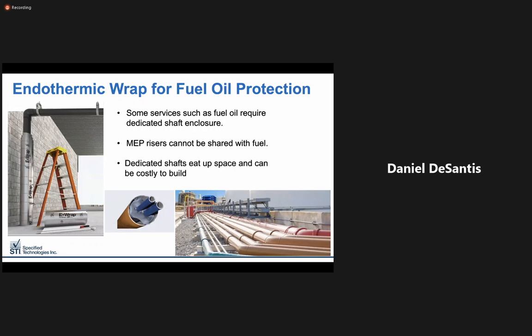Before we move on to specific solutions, let's recap. Fuel oil means dedicated shaft enclosure. Existing MEP risers still require a shaft within a shaft for full compliance. If space and cost are important considerations, endothermic wrap may be the correct solution for this aspect of your job. Also keep in mind that E-wrap can be used in conjunction with other methods of enclosure, such as CMU and drywall. In these cases where fuel oil piping exits the traditional shaft enclosure, the penetration would be fire stopped as a typical through penetration, and endothermic wrap would be butted against the substrate.